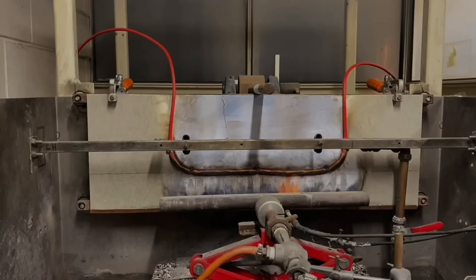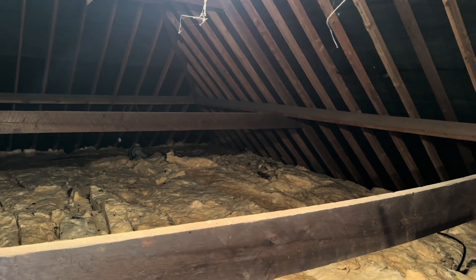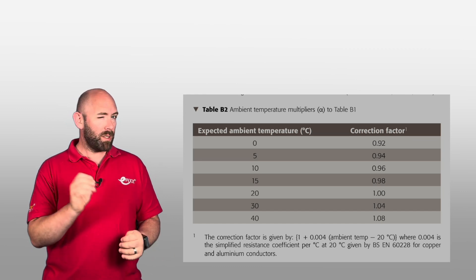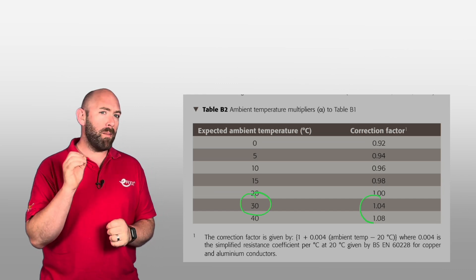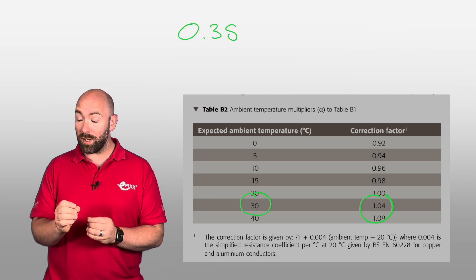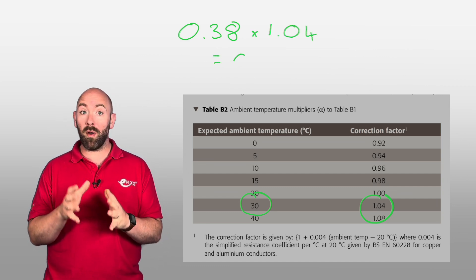These values are stated with the cable at 20 degrees Celsius, and temperature can have a significant impact on resistance — the hotter a cable, the higher the resistance. So if your cable is installed in a location with an ambient temperature of 30 degrees, the resistance is going to be higher. Table B2 gives us ambient temperature multipliers for Table B1. So if our cable is in an area at 30 degrees Celsius, we multiply our 0.38 ohms by 1.04, which increases the resistance to 0.4 ohms.